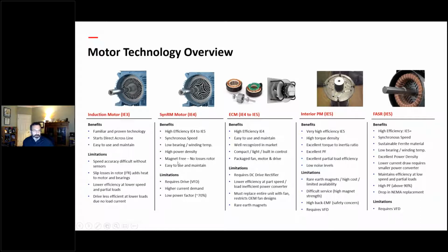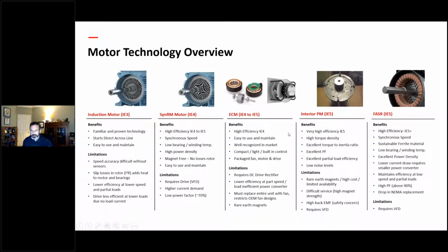Synchronous reluctance motors also have no magnets in them. So a lot of these other technologies over here to get to the higher efficiencies add magnets. And you add magnets basically to do some of the work of the stator. So remember I said you got losses in the rotor, you got losses in the stator. If the stator doesn't have to work as hard, there's less losses in the stator, and that's what the magnets do. But if I can do some of the work of the stator with a magnet, that means that the stator works less hard, which means there's less losses in it, and I get to higher efficiency.